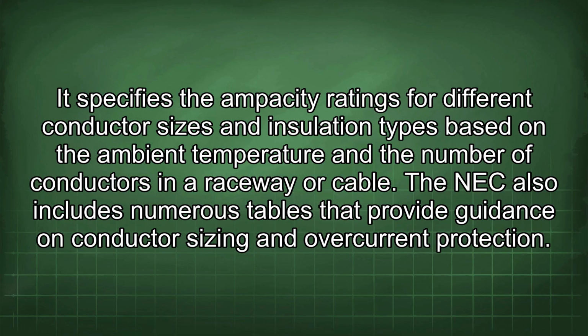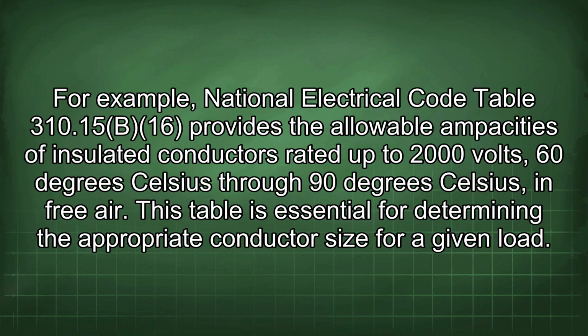The NEC also includes numerous tables that provide guidance on conductor sizing and overcurrent protection. For example, National Electrical Code Table 310.15(B)(16) provides the allowable ampacities of insulated conductors rated up to 2000 volts, 60 degrees Celsius through 90 degrees Celsius in free air. This table is essential for determining the appropriate conductor size for a given load.